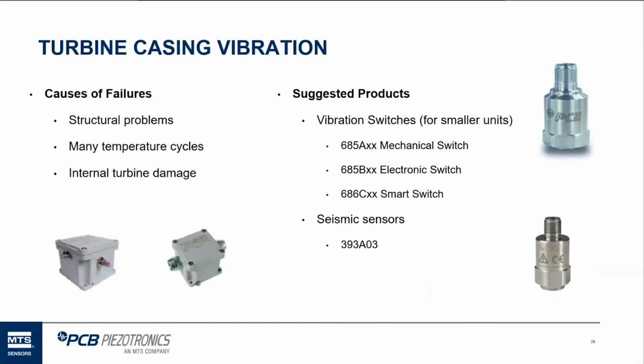Casing vibration. I pushed this a lot for really small hydro plants for a long time. Casing vibration on a small turbine is really easy and inexpensive to monitor. That can be caused by temperature cycles that change a lot. They start hot and cold during their run cycles, and they start to wear out, with internal damage and structural problems around the actual unit. So for smaller units, I like to push, and I have been successful in getting customers to purchase just vibration switches, real simple, inexpensive vibration products that can turn the turbine off if it starts to vibrate too much. Some of them are really simple, like our mechanical switches, the 685A versions. They're just simple.